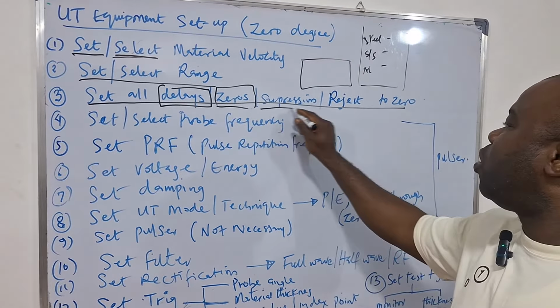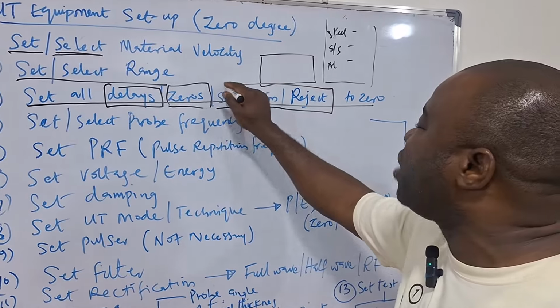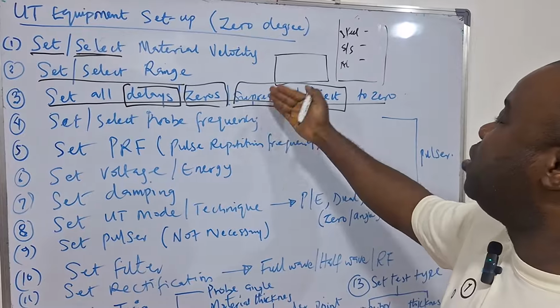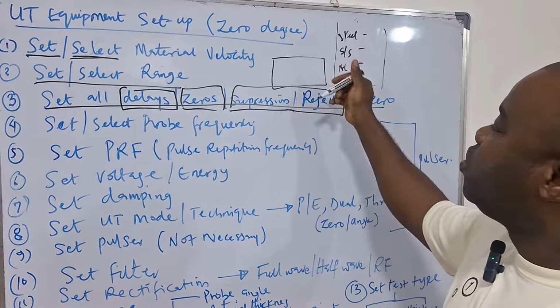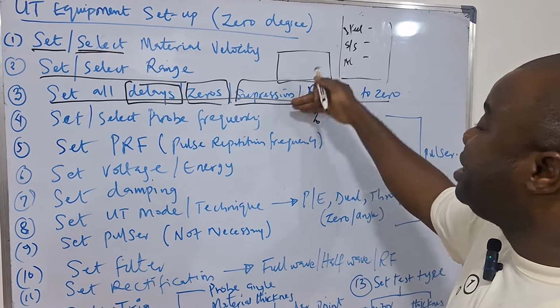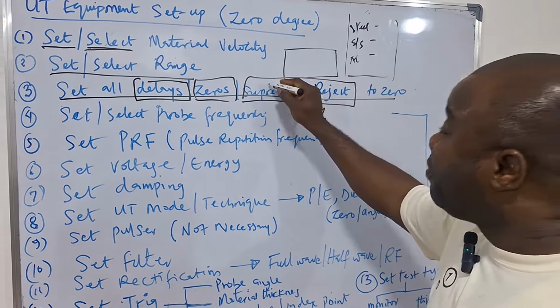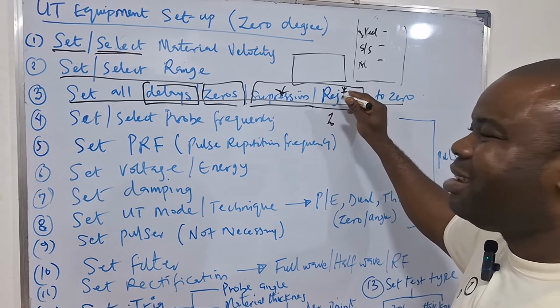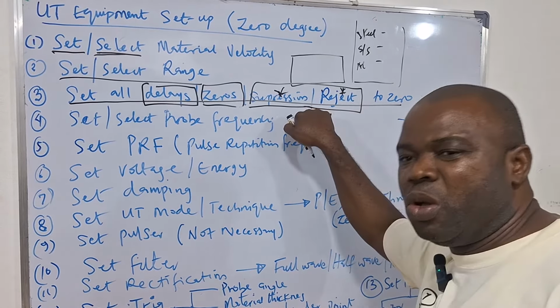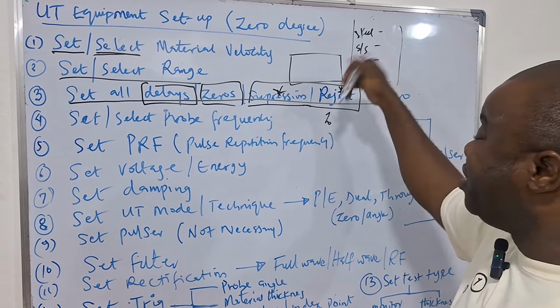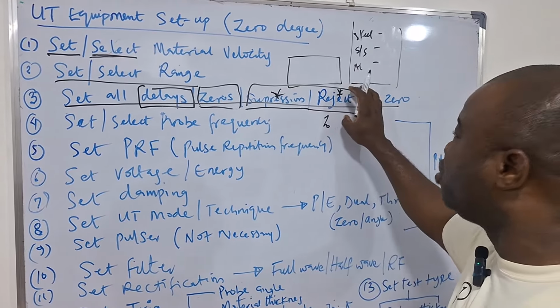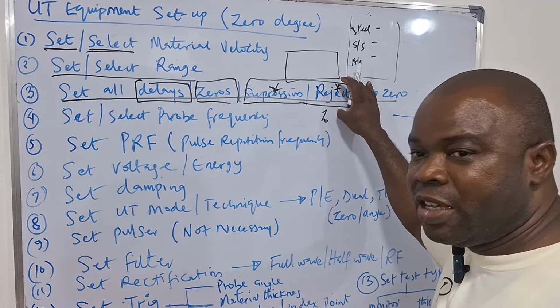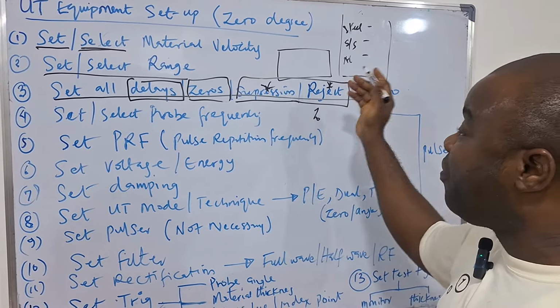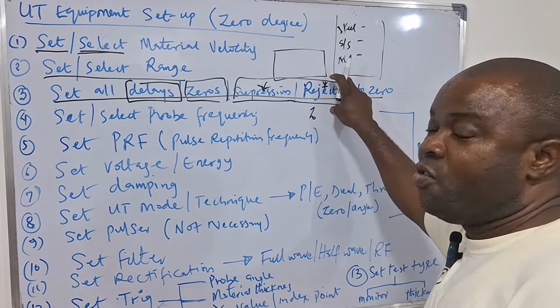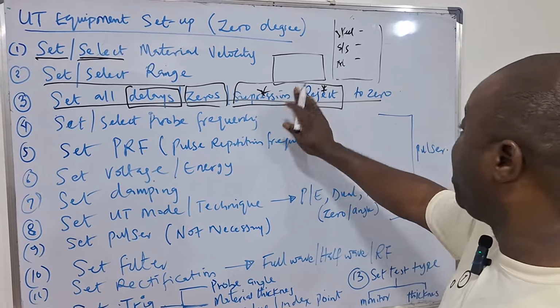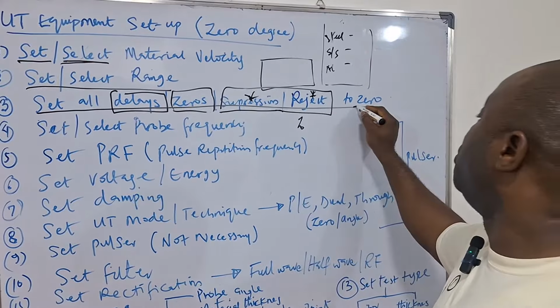Some units have what we call suppression. Suppression and reject are actually the same thing -- it depends on the nomenclature the machine uses. Normally it will be in percentage, so please set this to 0. Especially for suppression and reject, most of the jobs you will do at your basic level, and the majority of UT jobs, don't need it. So stay away from suppression and reject, because it will definitely affect whatever you're seeing in your A-scan. Do not go there if you don't need it. So you set all of this to 0.